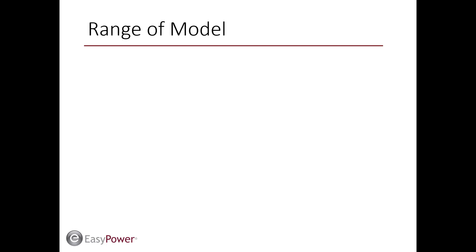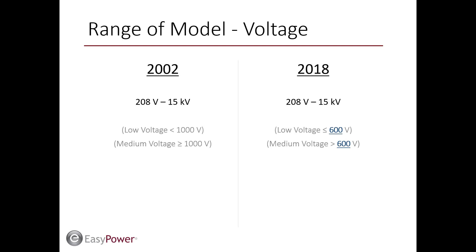Range of model: the IEEE 1584 arc flash model is an empirically derived model based on data observed during testing. Due to testing limitations, data is only available for certain system parameters, which define the range of model. Similar to 2002, the 2018 model is only considered to yield consistent results within the recommended range of parameters. The supported range of voltage remains unchanged at 208 volts through 15,000 volts. However, the threshold between low voltage and medium voltage has changed from 1,000 volts to 600 volts, which will have an effect during the calculation process.